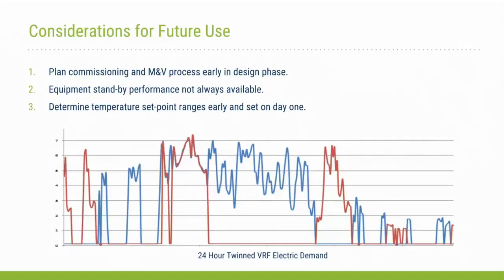For this system, we found just a continuous 300-watt controlled power demand. That adds up for a building that's trying to target a 15 for energy use intensity. As we saw, there were some challenges with controls integration for set-point control. We had to tighten that several months after occupancy, and some tenants were initially taken off guard when they could have a wider range and it was narrowed later on. So it's important to get players from the manufacturer and the controls vendor in as early as possible so that can be set up as early as possible.